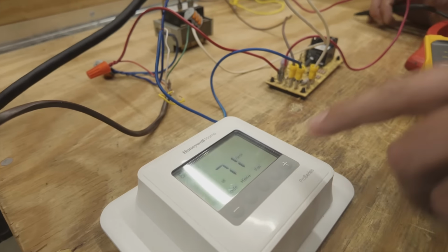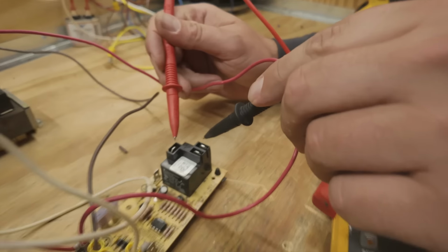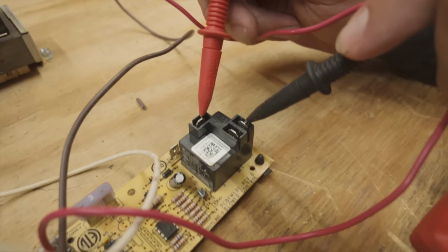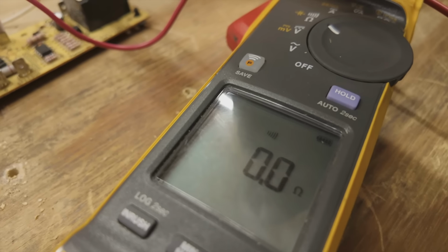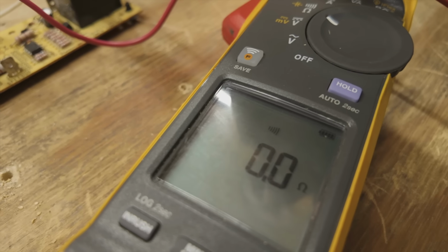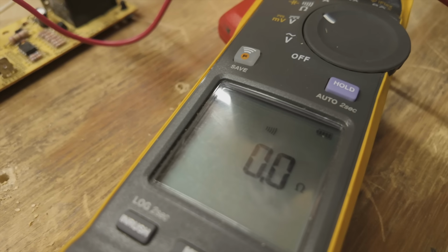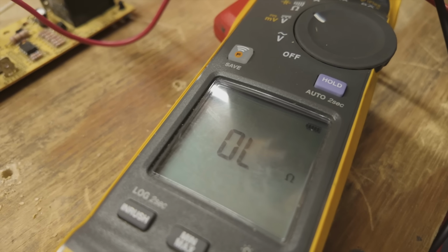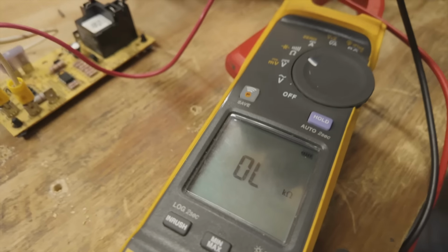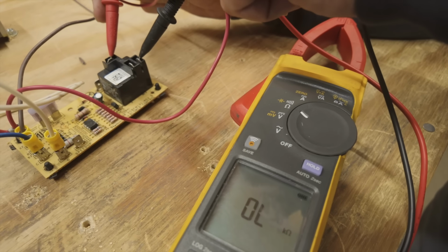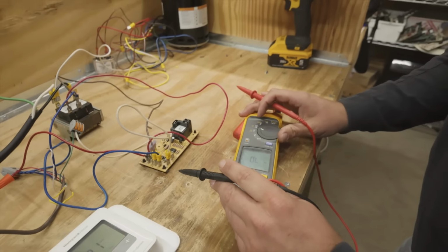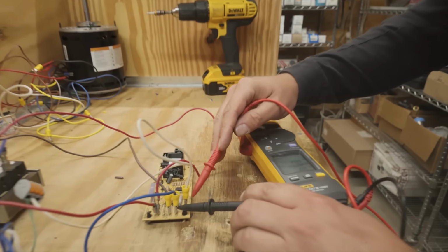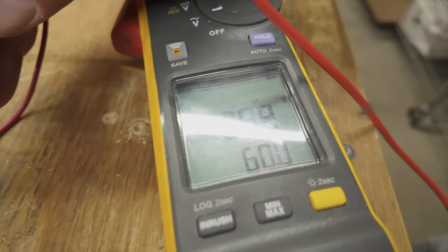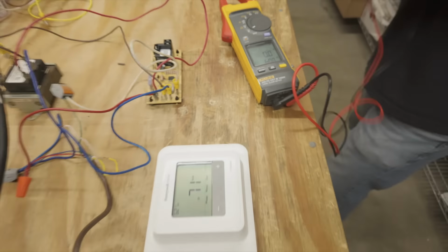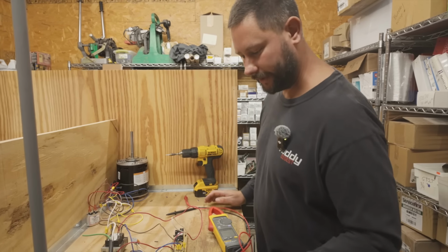All right, so that means if we take and go ahead and give a call to the board, go to this normally closed contact. Oh, heard thermostat click. Should have a little bit of a delay though, and it does. Oh, there it goes. Now this normally closed is open now. Normally closed, opened. And we did send voltage, right? Let's see. Do we have voltage? 29 volts.